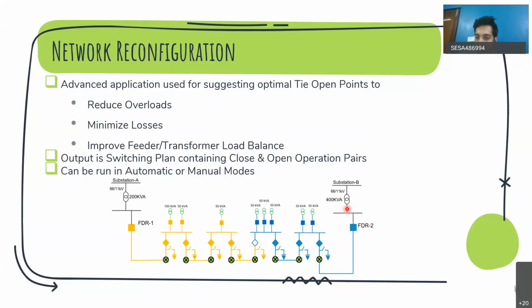Okay. Similarly, if you see this side, it is a 400 kVA power transformer and the feeder is feeding 5 DTs of 50 kVA. So that is 250 in total. Okay. So this is running at 100% loading and this feeder is running at maybe around 60% loading. So when you run this network reconfiguration either automatically or manually, it will suggest that this is getting overloaded. Please shift some load to this feeder. So it will say, okay, you open this switch and close this switch so that this transformer will now be fed by feeder 2.